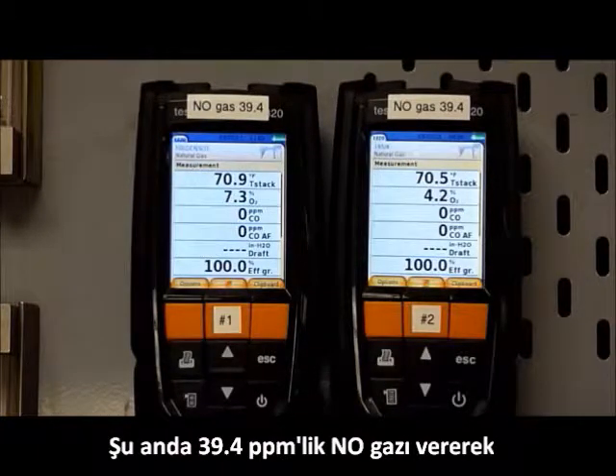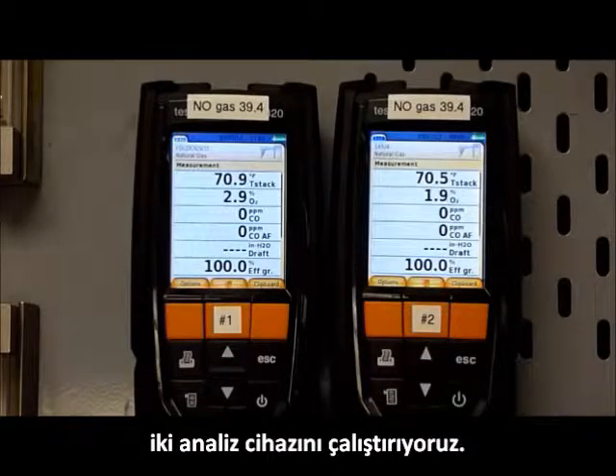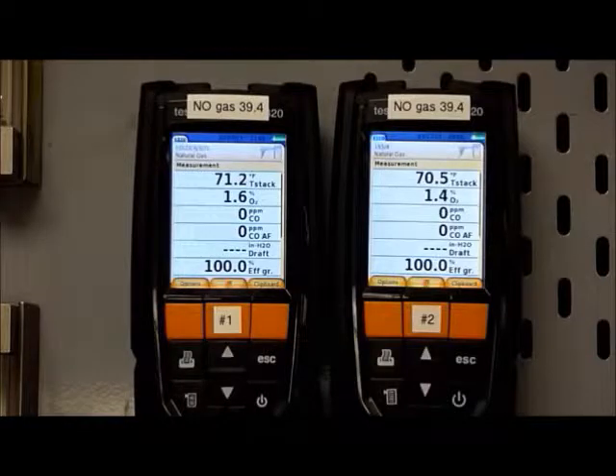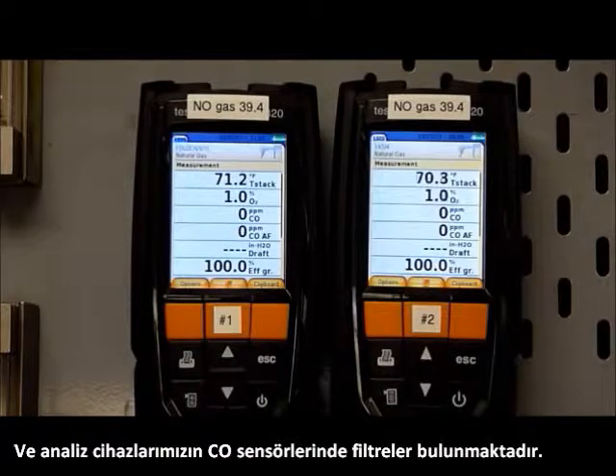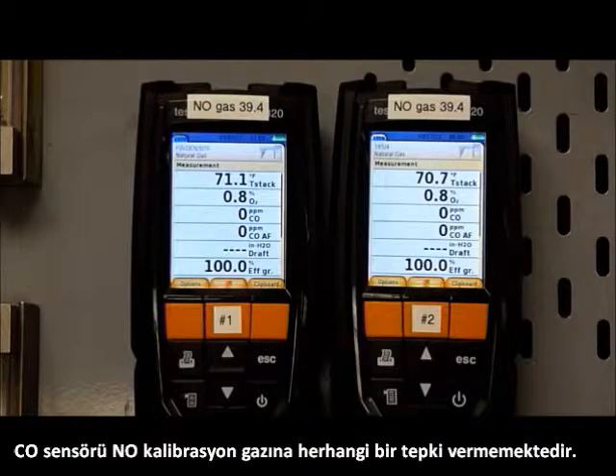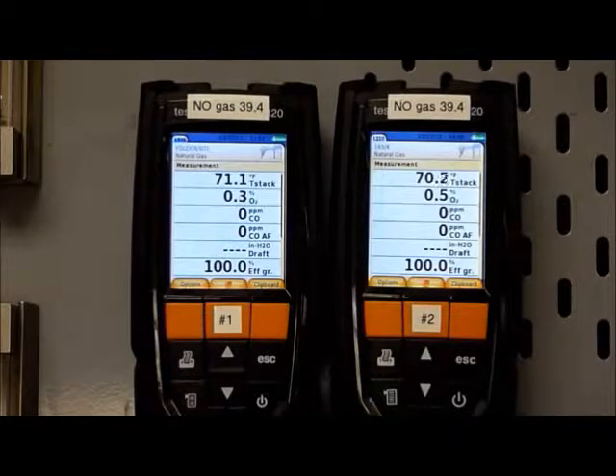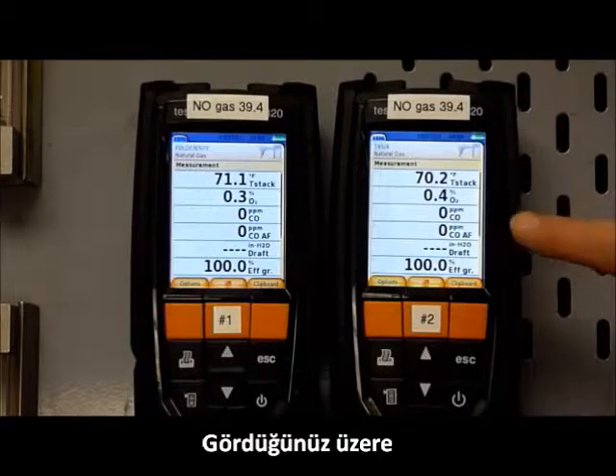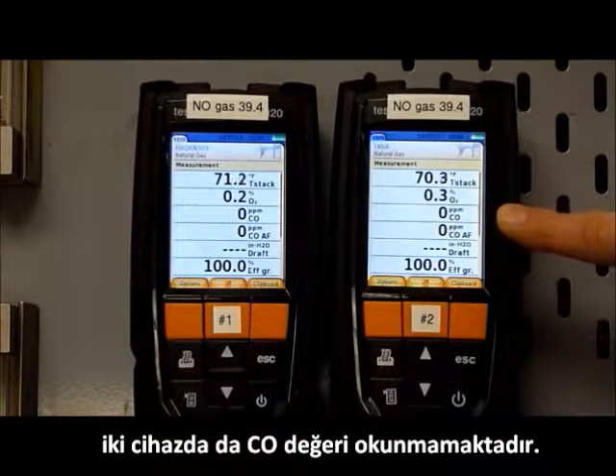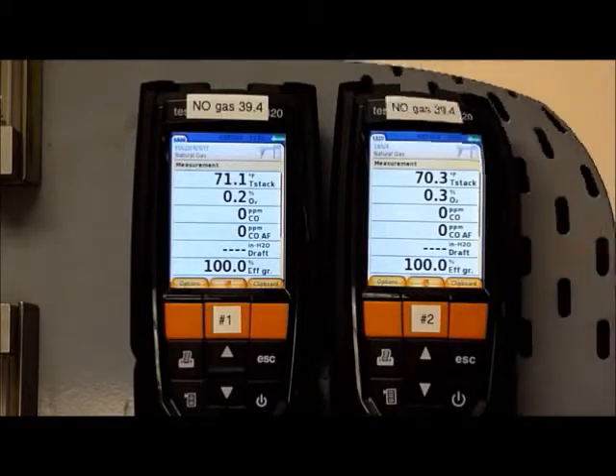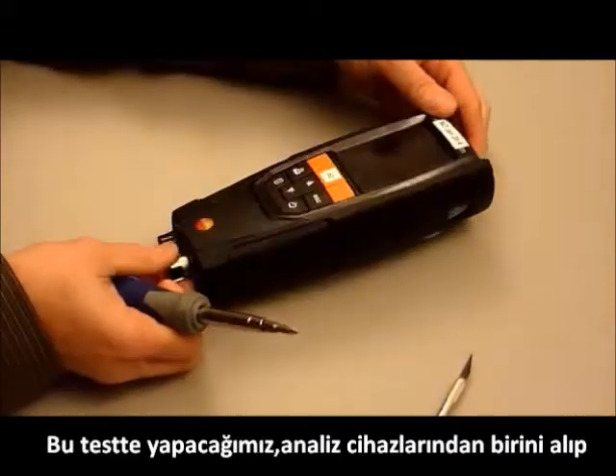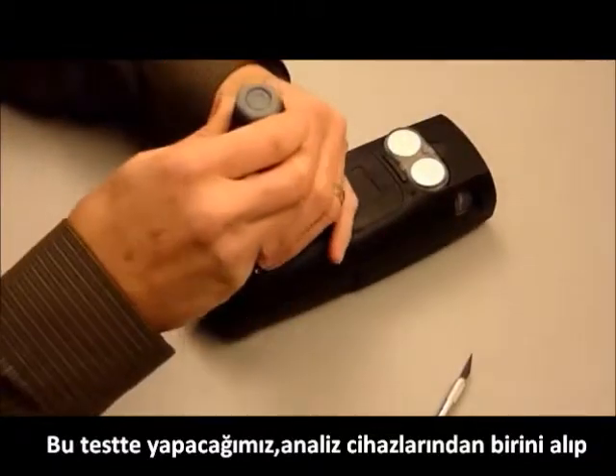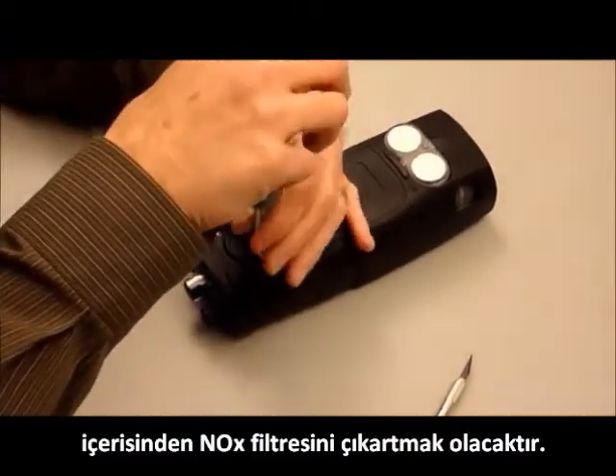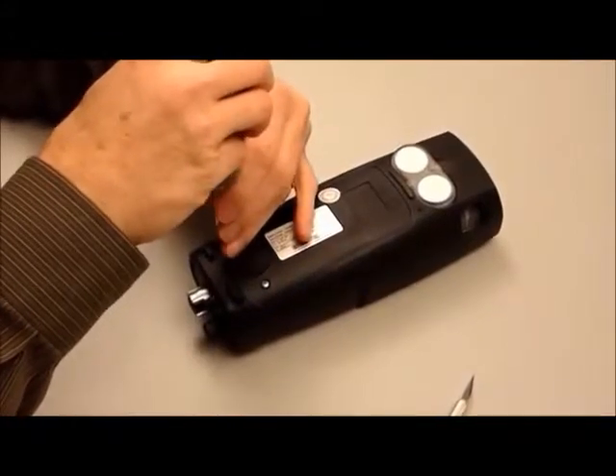Right now we're running two analyzers on a NO gas at 39.4 ppm, and as our analyzers use filters on the CO sensor, the CO sensor will not respond to the NO calibration gas. As you can see right here, we have no reading on CO on either of the instruments. Part of this test, what we're going to do is take one of our analyzers and remove the NOx filter from the analyzer.